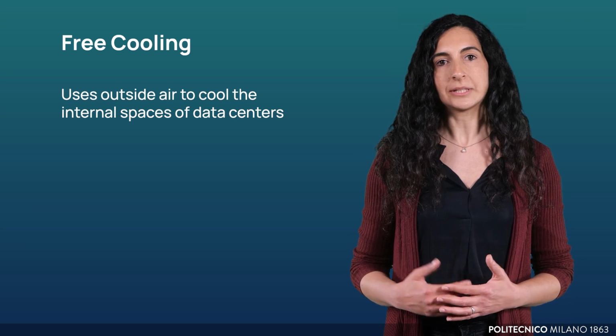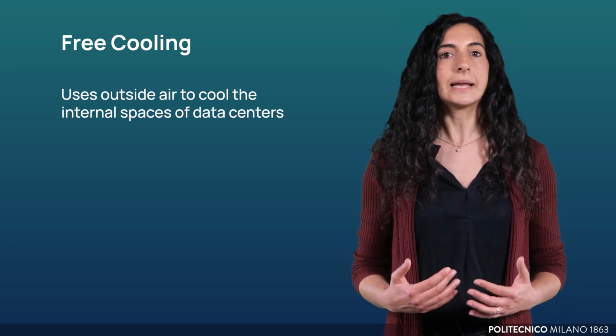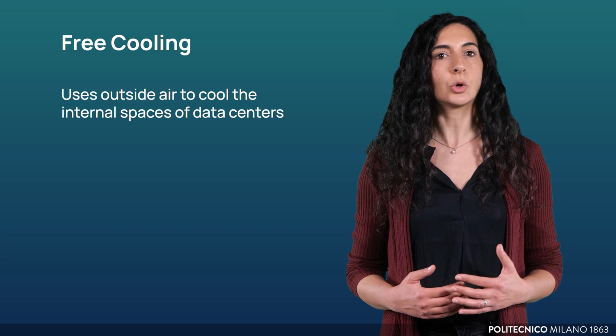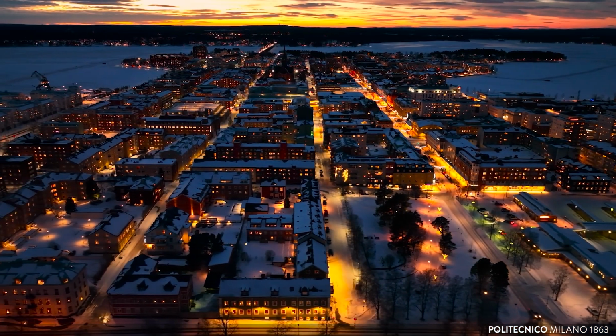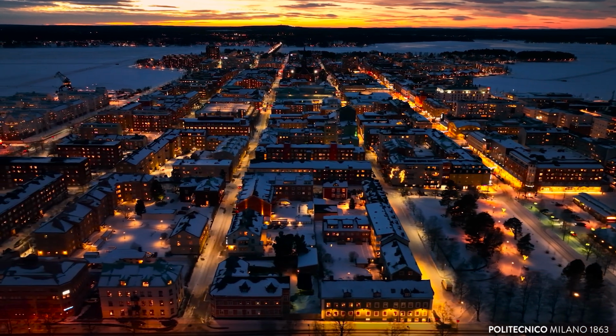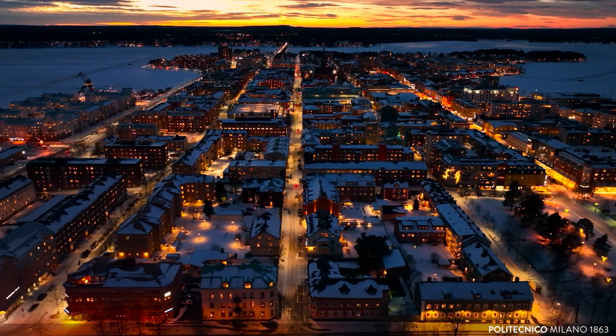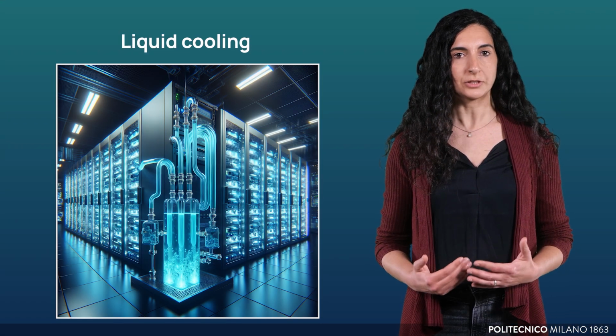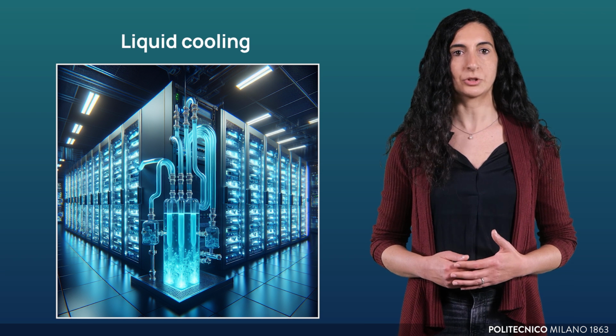Another way to reduce energy consumption related to cooling is to utilize advanced and highly efficient cooling technologies, especially in buildings and data centers. Among these is free cooling, which uses outside air to cool the internal spaces of data centers. This technique has led to a concentration of data centers in the coldest areas of the planet. For example, Meta's data center in Luleå, in northern Sweden, makes extensive use of free cooling thanks to the favorable climate conditions. Liquid cooling uses water or other fluids to absorb the heat generated by servers.